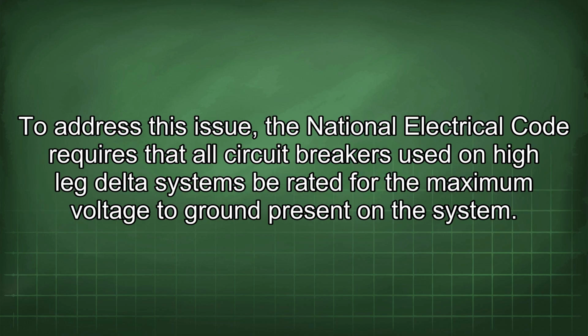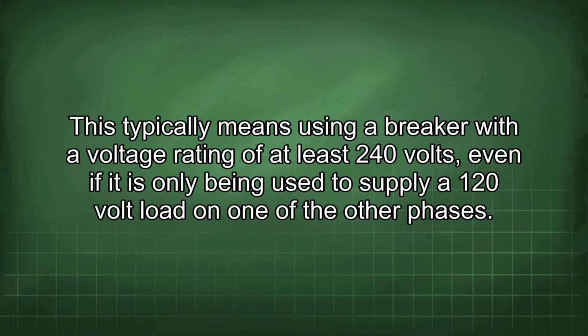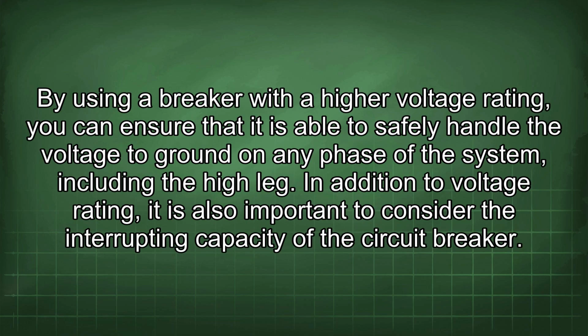To address this issue, the National Electrical Code requires that all circuit breakers used on high-leg delta systems be rated for the maximum voltage to ground present in the system. This typically means using a breaker with a voltage rating of at least 240 volts, even if it is only being used to supply a 120-volt load on one of the other phases. By using a breaker with a higher voltage rating, you can ensure that it is able to safely handle the voltage to ground on any phase of the system, including the high leg.